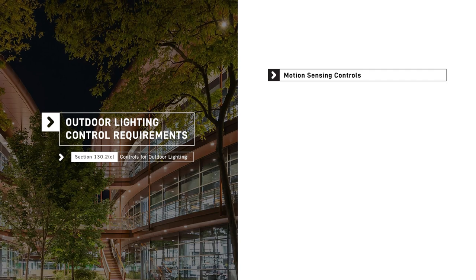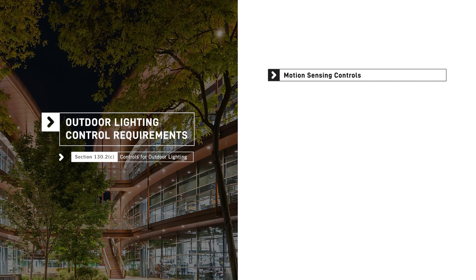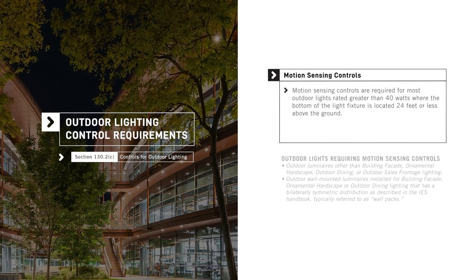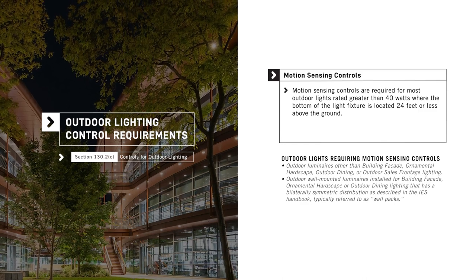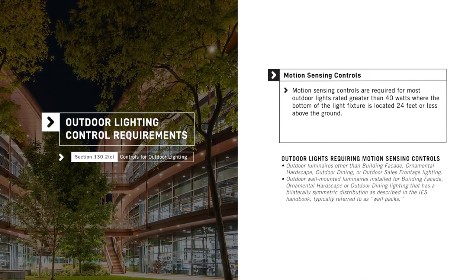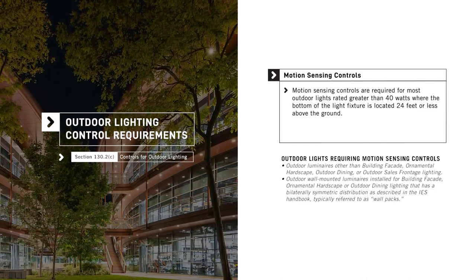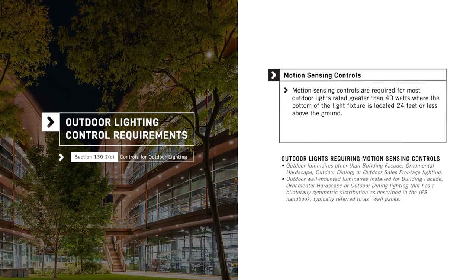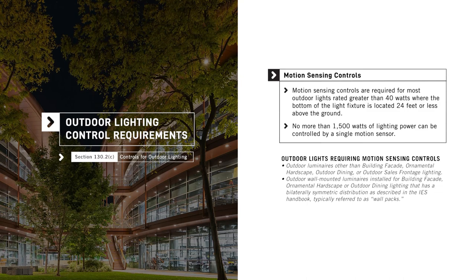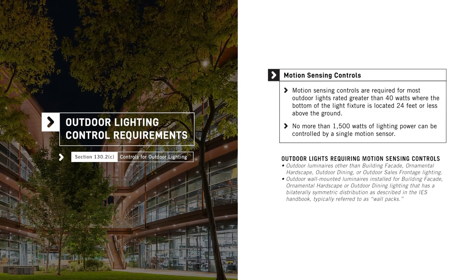Motion sensing devices control lighting based on detected occupancy by reducing or turning off the outdoor lighting in the area when that area is vacant. Motion sensing controls are required for most outdoor lights rated greater than 40 watts, where the bottom of the light fixture is located 24 feet or less above ground. No more than 1500 watts of lighting power can be controlled by a single motion sensor.